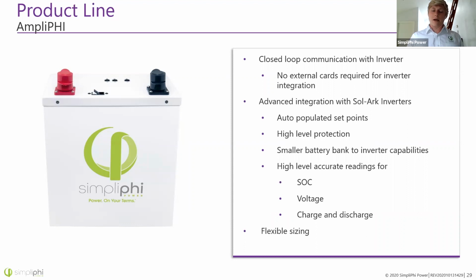Another big advantage to this battery is it allows for flexible sizing. This battery can actually limit its own charge and discharge rate by communicating with the solar inverter. That means if you have a customer wanting to install a solar inverter with just 1 or 2 batteries, you know that's not possible with the Phi battery because of the C/2 rate. However, with the AmpliPHI battery, it can communicate to the solar inverter and limit its own charge and discharge rates, so you can start with just 1 or 2 batteries on that inverter and then increase as you go.